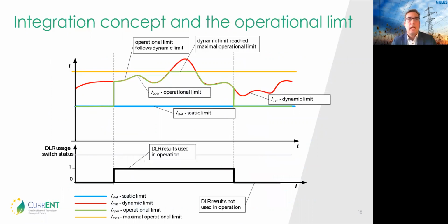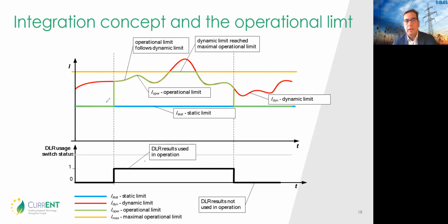Regarding the integration concept, the operational limit, which was introduced in our SCADA system, was invented just for this purpose: to integrate dynamic thermal values from DLR. It may be static, dynamic, or limited dynamic. Once the operator engages the use of the dynamic limit, the operational limit equals the dynamic value until it reaches the maximum allowed thermal current for that line.